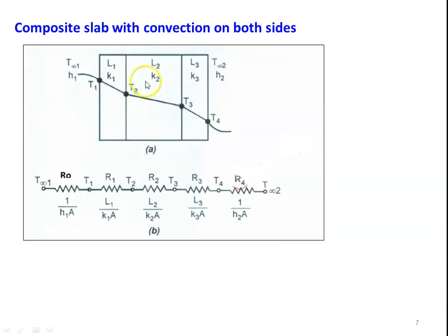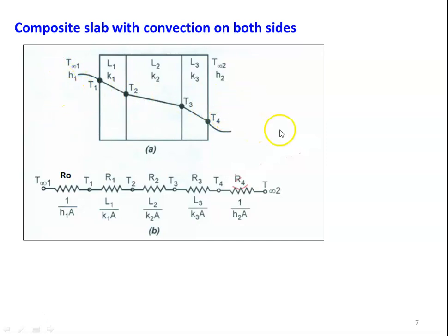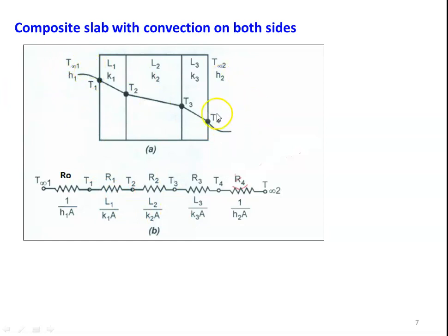Now consider the composite slab with convection on both sides — for example, a boiler wall where hot gases circulate inside and atmospheric air is outside. The same slab configuration now has convection on both sides. Hot gases are on the left side, with different insulating layers, and atmospheric air is outside. To minimize heat transfer, we need sufficient insulation thickness. There are now convection resistances on both sides in addition to the conduction resistances of the three slabs.